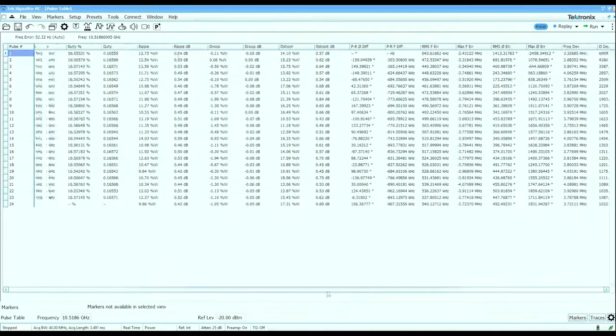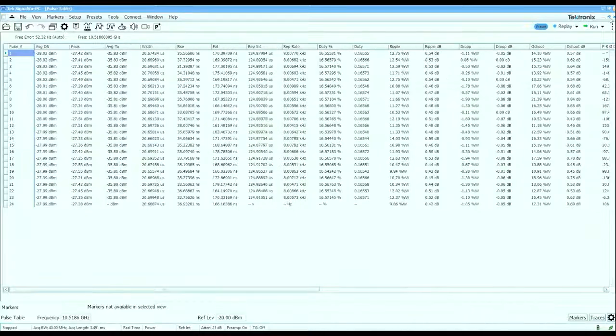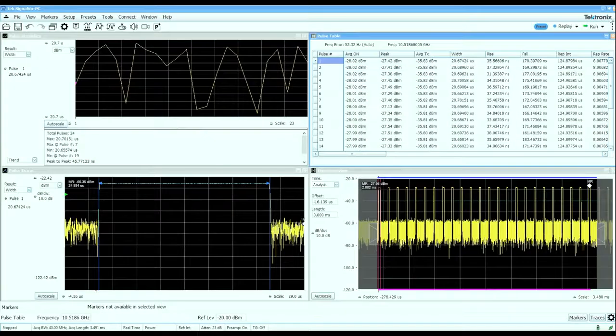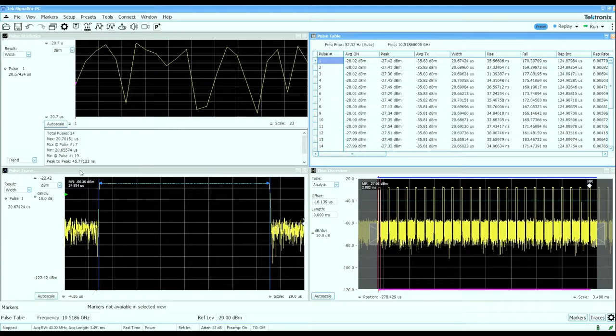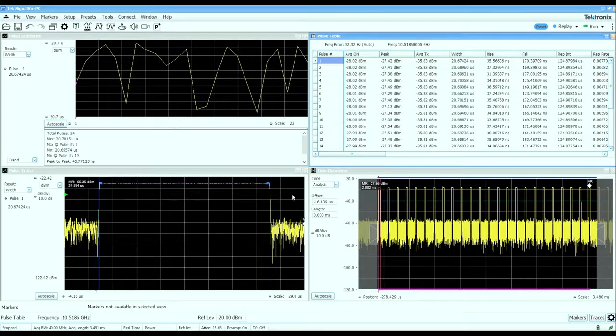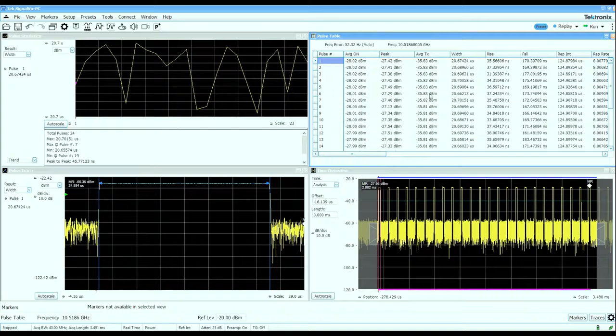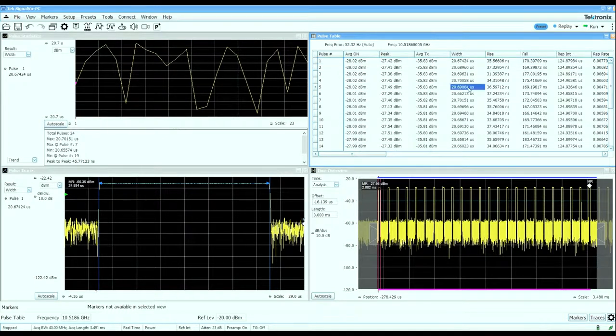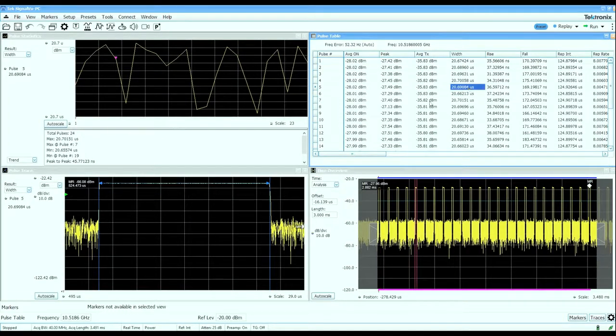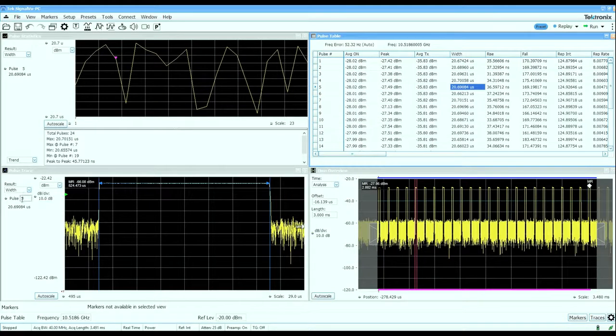This pulse trace display can show you any selected measurement on any selected pulse. For example, if I'm looking at the pulse width of pulse number five, I can click on that cell and see the pulse width measurement made on pulse number five.